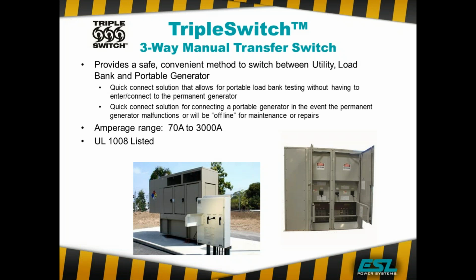But it now provides you with a design where you have a UL 1008 listed transfer switch connected through a UL 1008 listed ATS, and you're providing your clients with a nice, seamless type of design. So that is unique in the marketplace. You'll see a lot of other variations that talk about how they're listed to the standard, but there really is no UL 1008 standard with both male and female cams in it.